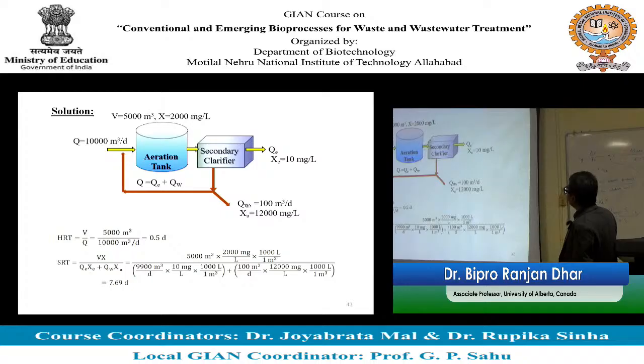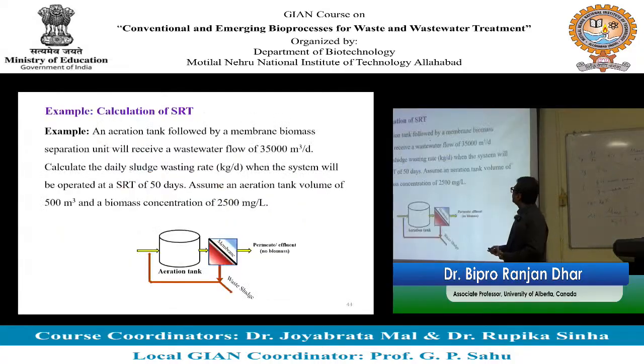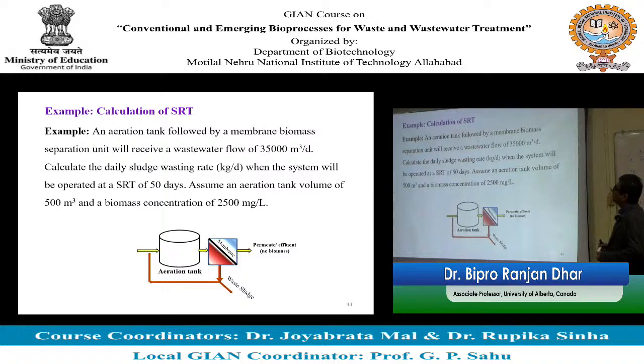So yeah, I just put all the information that we have in the equation, HRT = V over Q, and for SRT we can simply use this equation. So SRT is going to be 7.69 days, right? And now the second example, calculation of SRT.